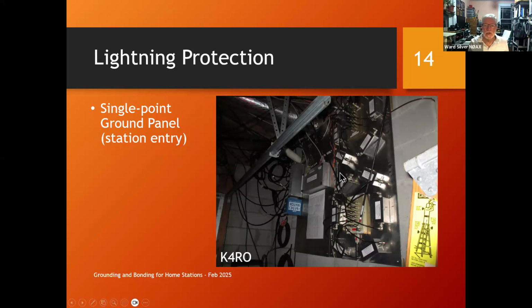You can see filters, switches, selectors, a stack match, all mounted on that panel, and the panel bonds it all together. Then this wire bonds it to the lightning protection system outside. Since he did this, he's lost exactly zero pieces of equipment, and it's been several years. This bonding together, making sure everything goes up and down together, really worked for him—so there's no opportunity for current flow between, say, a filter and a switch, or a stack match and a rotator controller. They're all at the same voltage. It's not zero, but they're all going up and down together.